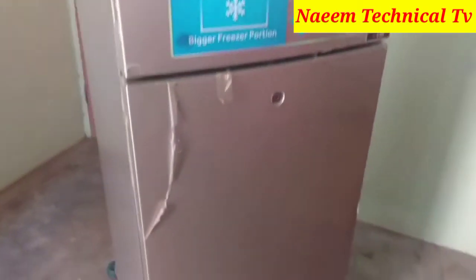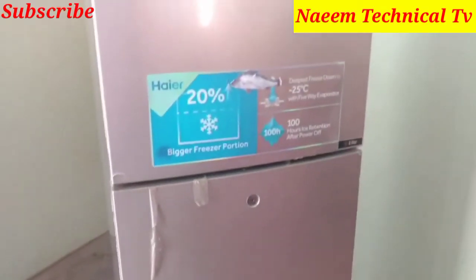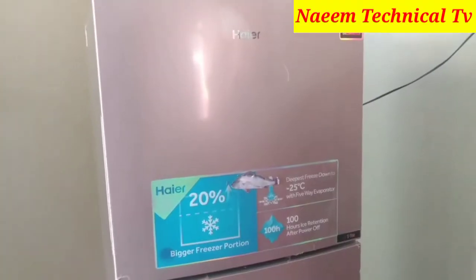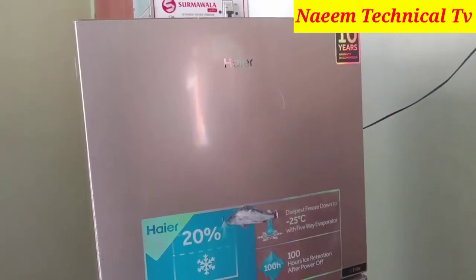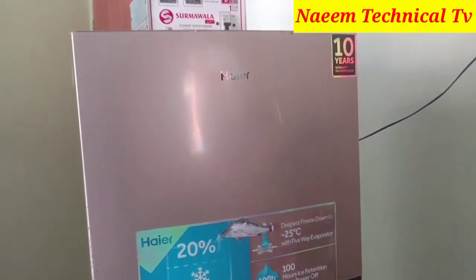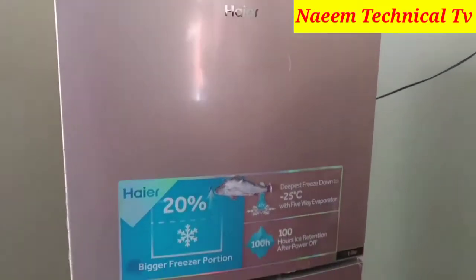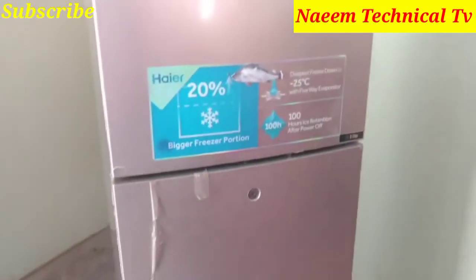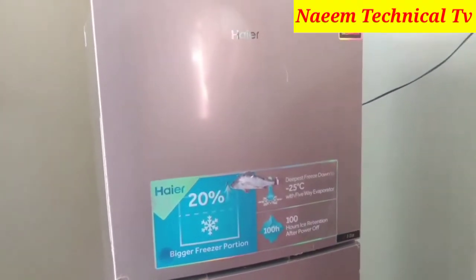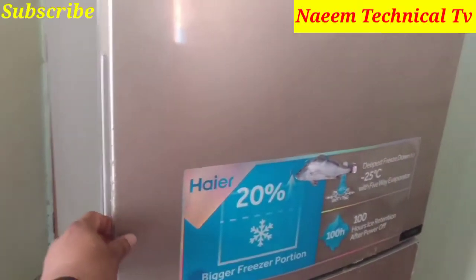This video is very special. The customer told me that he already called a technician to repair this refrigerator. The technician came, repaired all the damaged tubes, and charged the gas. But after gas charging, two new faults occurred — the refrigerator is taking too much time to make tough ice in the ice pots, and it is also continually dropping water drops from the suction pipe.